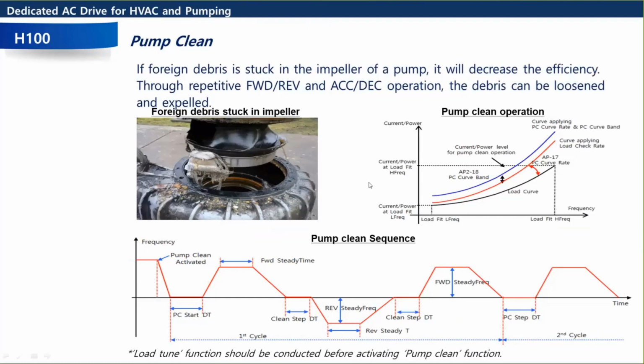There's a few different ways that you could enable this. You could have it enabled based on a current or a power consumption. So if we ever hit a high load, like a high amperage, then it'll automatically go into a pump clean. Or you could program one of those digital inputs. Again, P1 through P7 are fully programmable. So you could pick one and say, hey, I want this to be pump clean. And then you have a switch that you flip on, and then it goes into this pump clean mode.